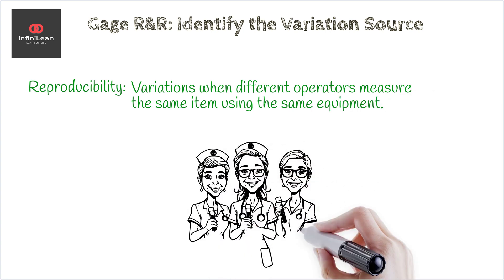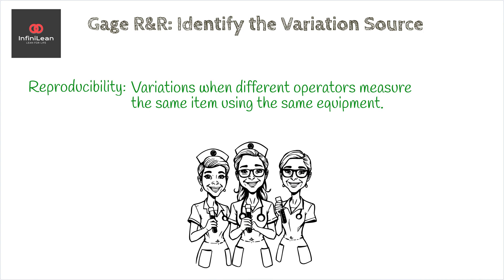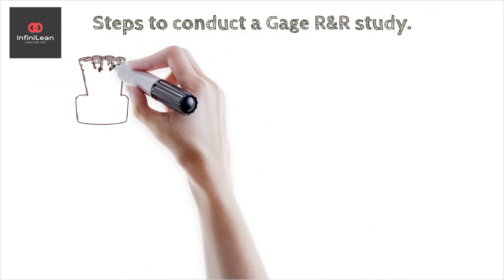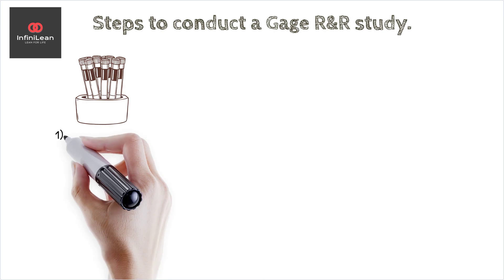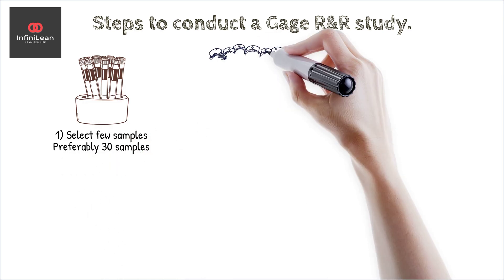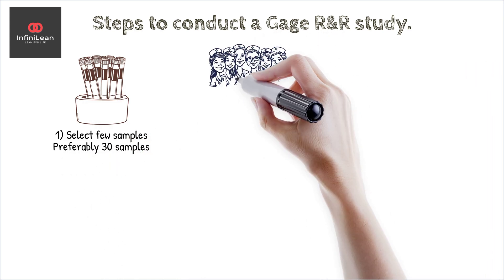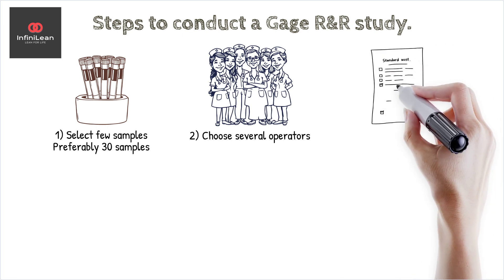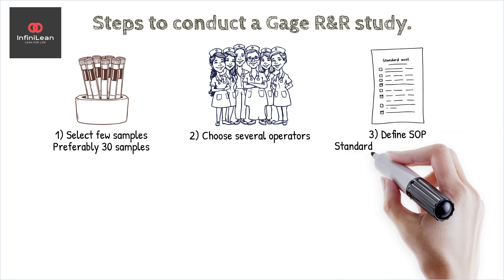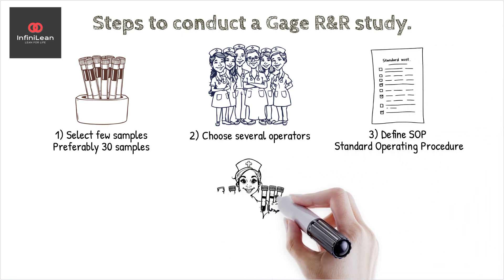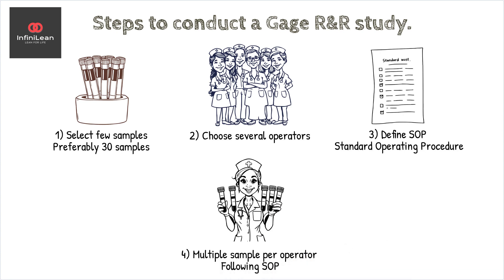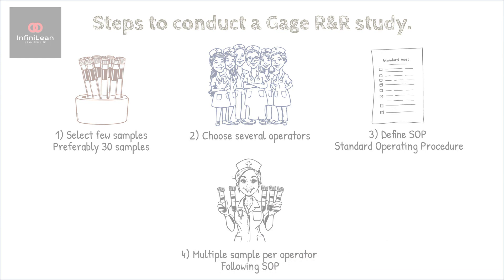So how do we conduct a Gauge R&R study? Typically, it involves selecting a few parts representing the full range of the process variation, choosing several operators, and defining the measurement process clearly. Each operator measures each part multiple times, strictly following the same procedure.